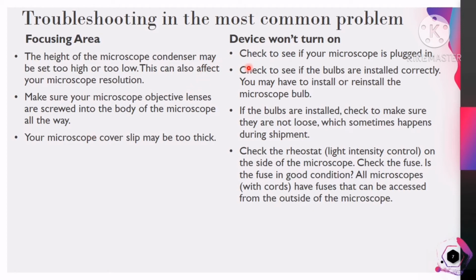The device won't turn on. If you happen to have this problem, you can check to see if your microscope is plugged in, check to see if the bulbs are installed correctly. You may have to install or reinstall the microscope bulb. If the bulbs are installed, check to make sure they are not loose, which sometimes happens during shipment. And check the rheostat, which is the light intensity control, on the side of the microscope. Check the fuse. All microscopes with cords have fuses that can be accessed from the outside of the microscope.